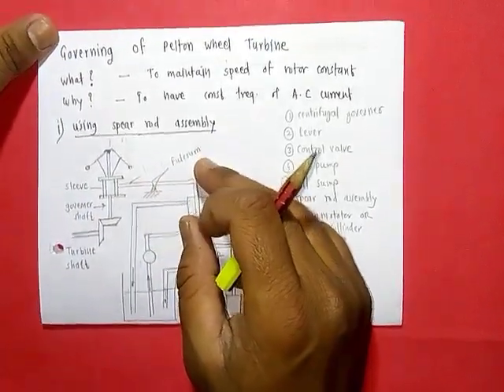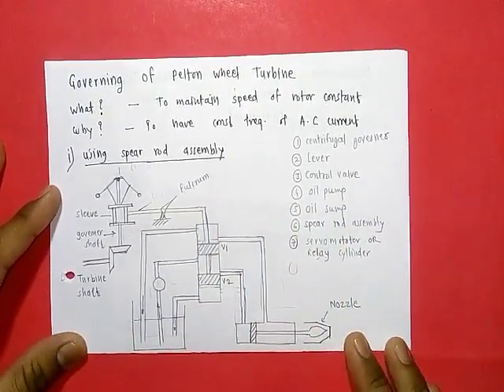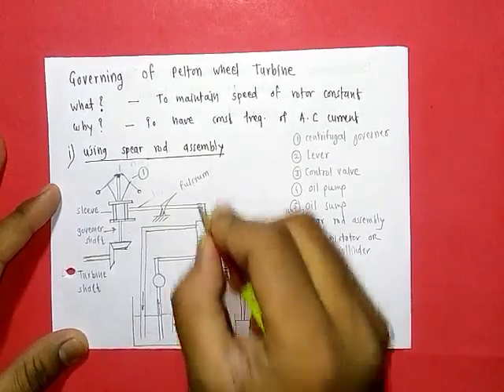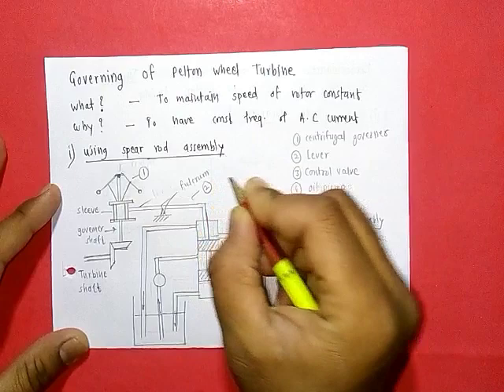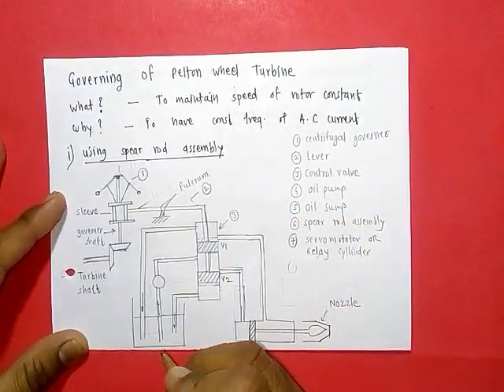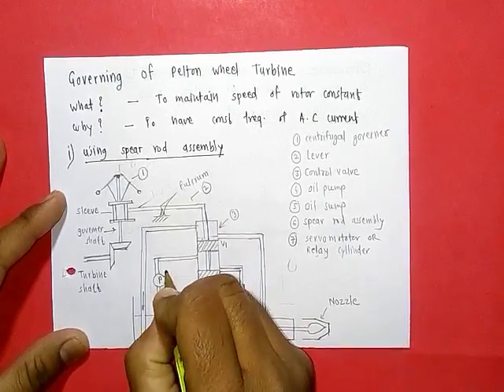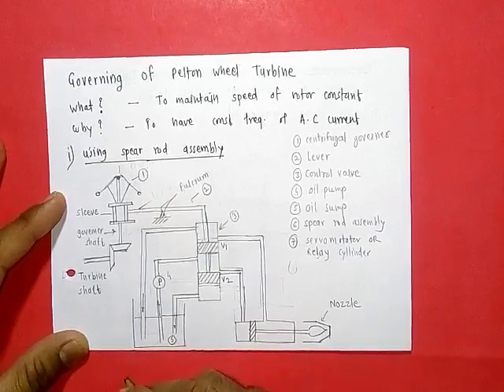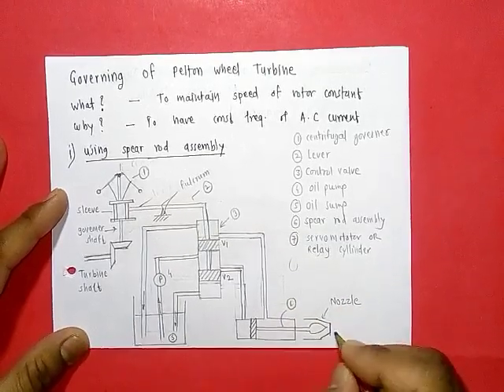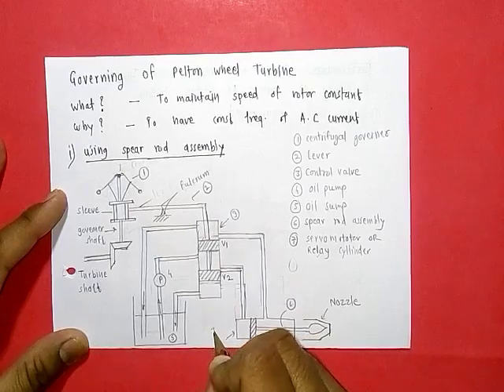The first method is using the spear rod assembly, used for Pelton wheel turbines. The governing mechanism consists of: a centrifugal governor working on centrifugal effect, a lever pivoted on a fulcrum, a control valve to control oil flow, an oil pump to carry oil from the sump to the control valve, an oil sump for storage, a spear rod assembly with a nozzle, and a servo motor or relay cylinder.